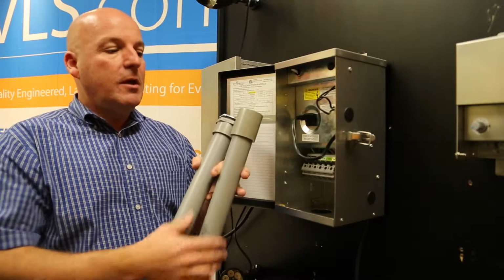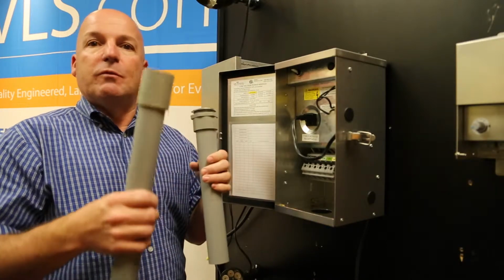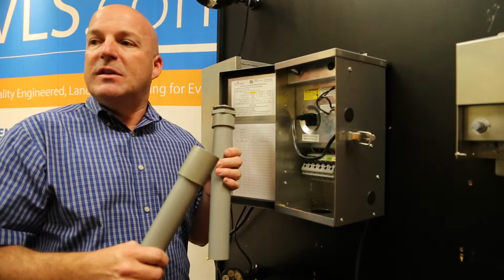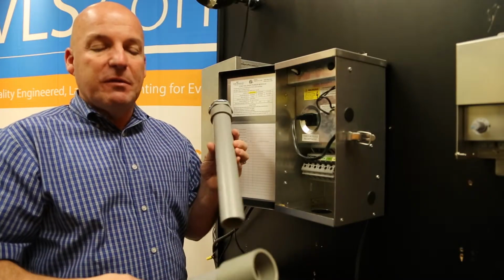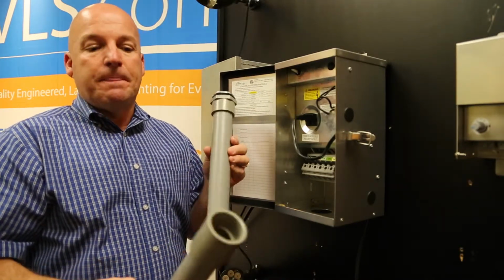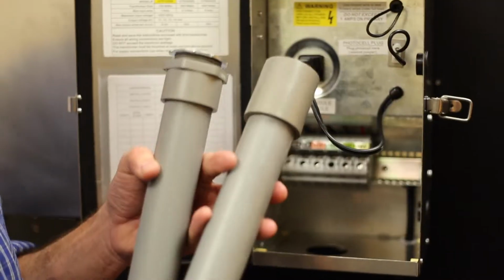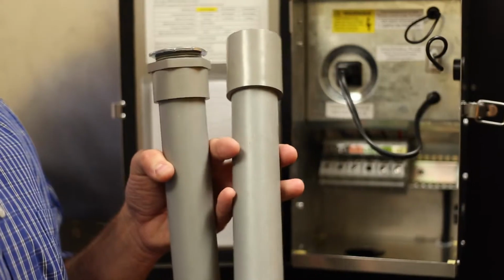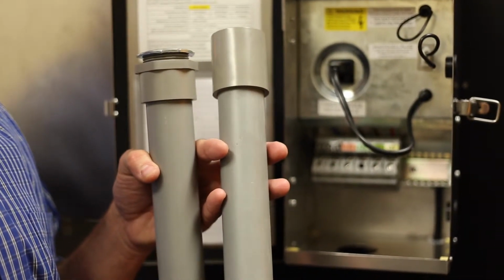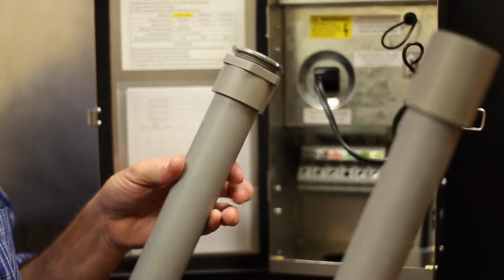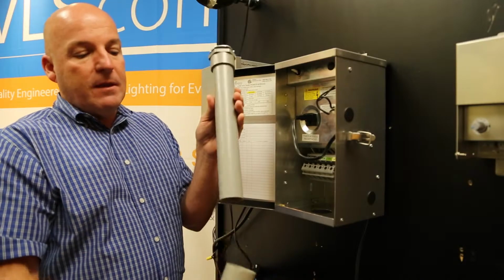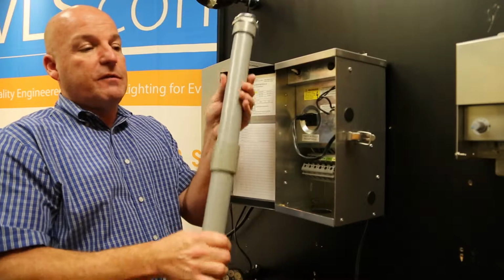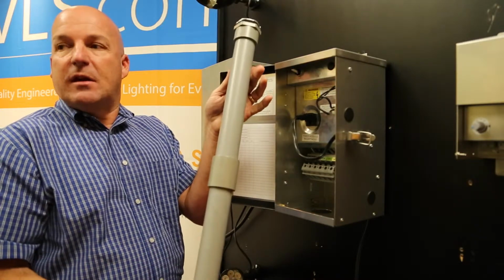I know we all do. So rather than have you run back to whatever supplier house you need to get these components, we provided them in the box. We give you 2 12-inch pieces. NEC states that the lowest a transformer can be to the ground is 12 inches. So we give you 2 of them, 12 inches long, with a coupling, giving you the ability to have a 24-inch piece of conduit.